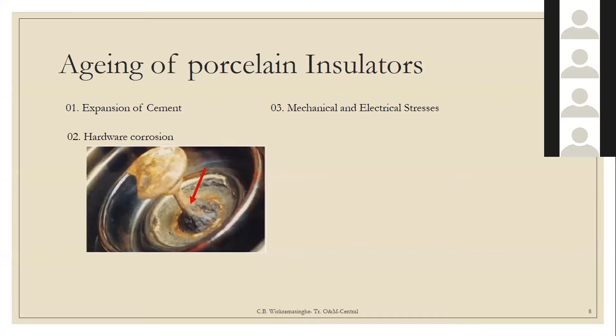So we cannot exactly say this is the period of an insulator, this is the age of an insulator. Aging depends on some variables like lightning, loading, coastal area, environment, atmospheric conditions, etc. And these are the two techniques currently used in the power system industry for online condition monitoring of insulators: the hypo test and electrical field mapping. As you can see, the person has to climb up that tower and get close to this box in order to measure the leakage current.